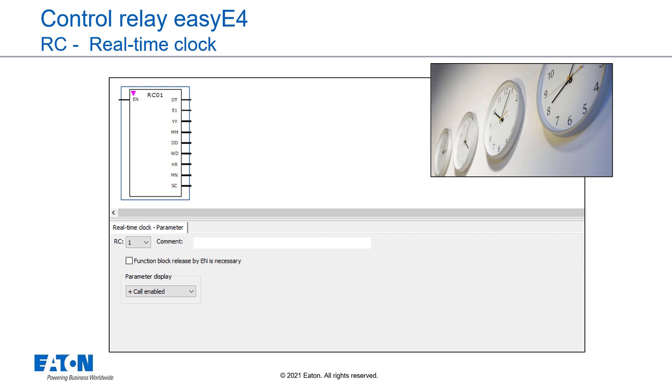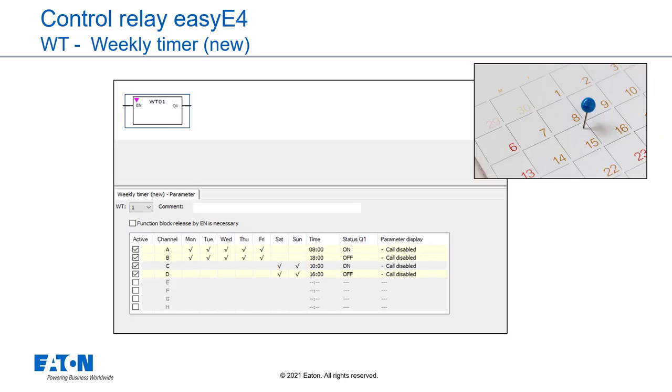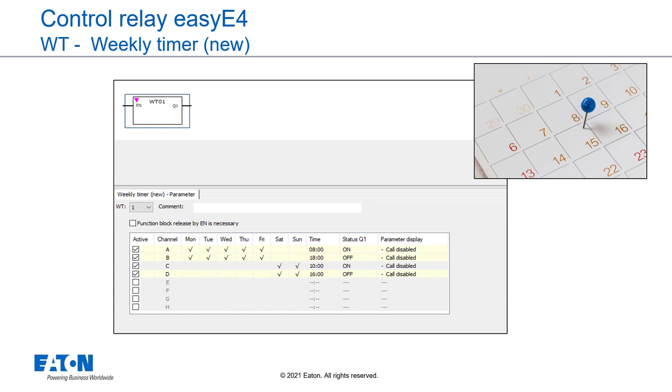Function block output DT signals whether the clock has been switched to daylight saving time. The weekly time switch function block WT for week table is a further development of the existing HW weekly timer function block. easyE4 base devices provides 32 weekly timers. With the weekly timer, recurring switching events can be parameterized in a simple manner and clearly in a table. This function block is specially designed to implement switching events that occur at set weekly cycles, for example different procedures for business days and weekends. Each of the 32 weekly timers can be parameterized with 8 switching events each. The settings are accurate to the minute and cannot be modified during runtime. That means they must be viewed as a set configuration.